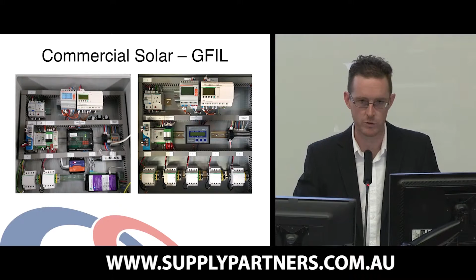Now, of course, most systems in the commercial space are less than 100 kilowatts because of STCs. I've seen some people putting in 100 kVA of AC inverter capacity, matched up with 99 kilowatts of DC module capacity. I think you're probably spending too much on your inverters, frankly. Aim for something like 90 kVA AC on your inverters, and think of that as being similar to 6 kilowatts of panels on a 5 kilowatt inverter. Network approvals can take a whole lot longer than the residential space, so if you haven't gone through it before, give yourself a bit of space.